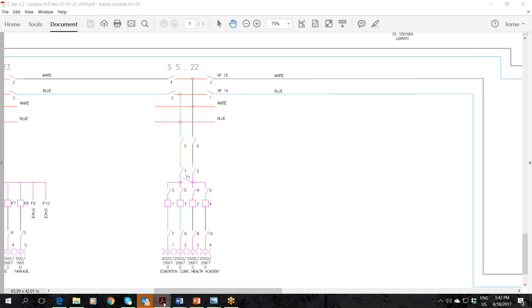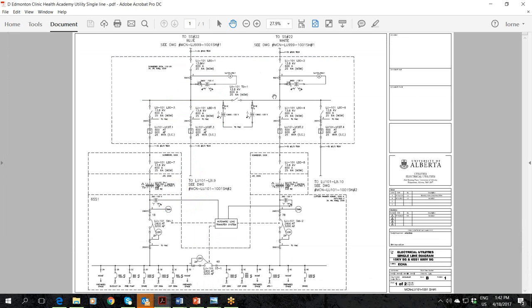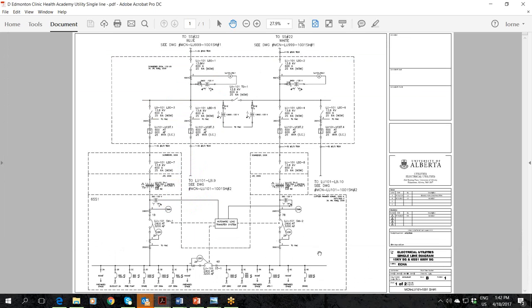So they own the equipment. The department owns the substation. Yes, but we operate it as the electrical utility. So in terms of operation, we have our demarcation point right at this bus. They own, operate, and maintain the feeder breakers down to the motor control centers and whatnot, and the step-down transformers. We operate the main-tie-main and do maintenance on those.